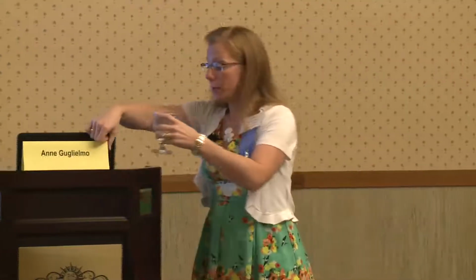We do train the surveyors, and we've told them that just because the bottle says 15-minute flush does not mean a plumbed eyewash station is required. The ANSI standard only requires it to be installed where there's a caustic or corrosive material in use within the space or area within the appropriate travel distance. So the answer back to the surveyor, whether clinical or life safety, when they say you need this here because I see a bottle with a 15-minute flush, the question is, what are your first aid measures? I'd prefer to use the term first aid that gets me through to that necessary 15-minute flush on the back of the bottle. At the end of the day, I don't think there's a manufacturer out there that doesn't put 15-minute flush just to be safe, right? We're in a day of litigation, everybody will sue every chance they get, so there isn't a manufacturer that isn't going to give you some sort of precaution. Again, knowing that the ANSI standard requires it for caustic and corrosive is key to having a successful observation either written or removed during the survey process.